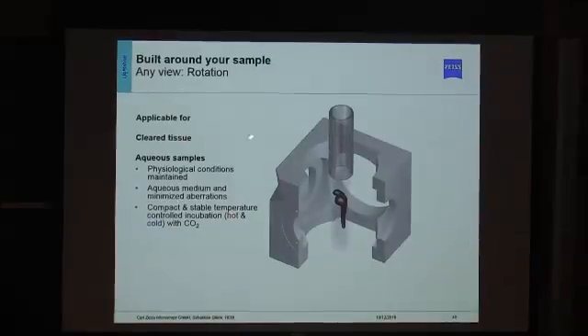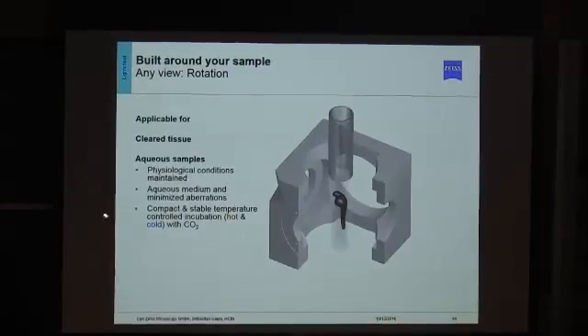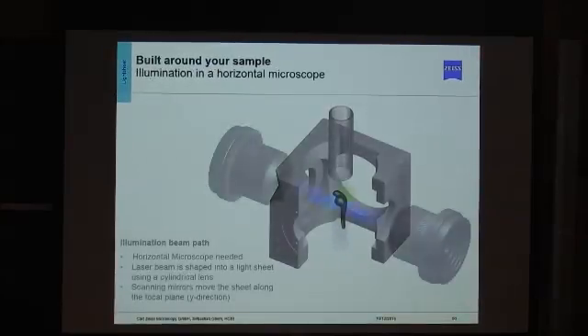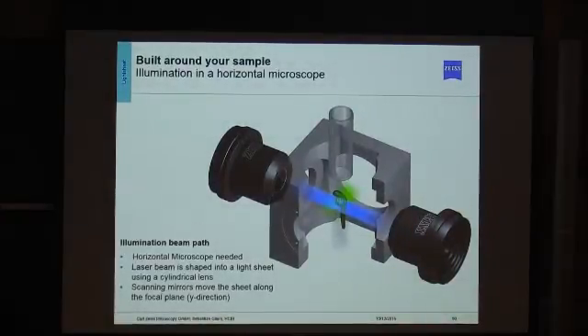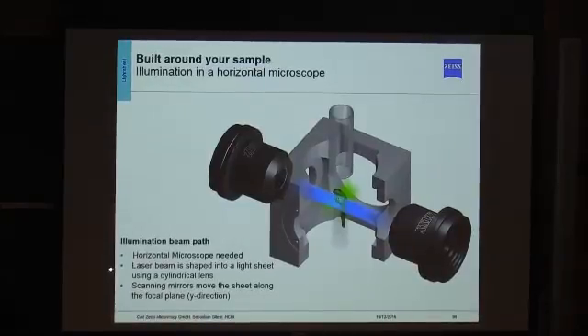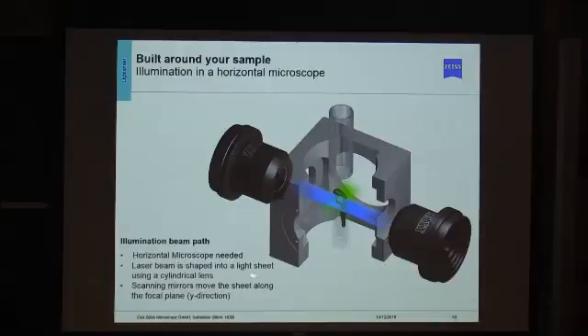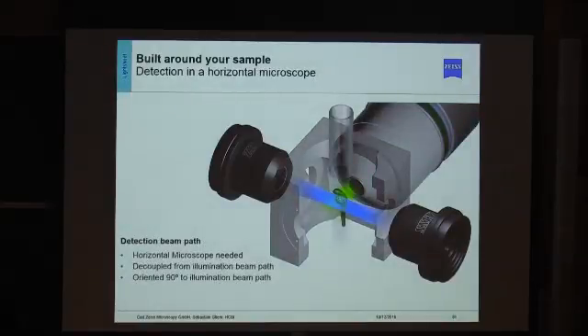The illumination light path in the light sheet microscope is different from other systems: the illumination light path is oriented horizontally, with the laser being shaped into a light sheet using cylindrical lenses. Scanning mirrors move this light sheet along the Y axis to scan over the sample. The key feature is that the detection objective sits perpendicular to the illumination — it is decoupled from the illumination. In other systems, you illuminate and detect along the same optical axis, exciting all focal planes along that axis. With light sheet illumination, you generate only a very thin layer of light, illuminating only the focal plane of the detection objective.